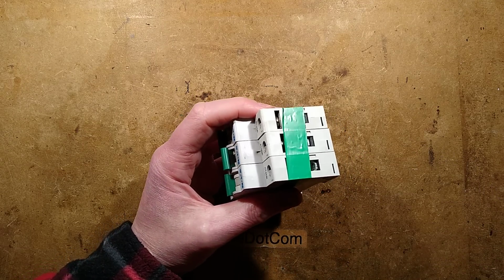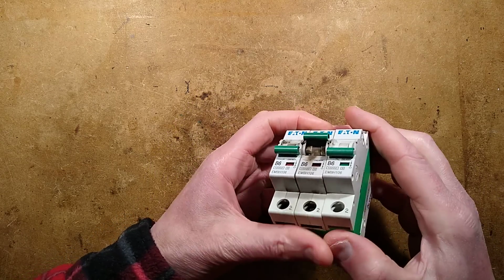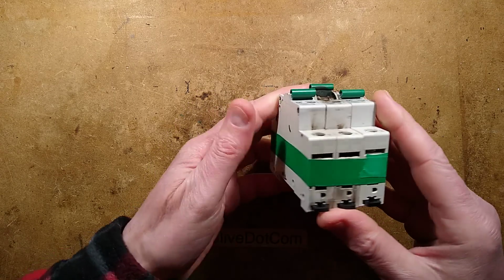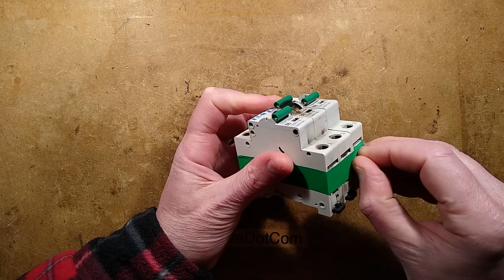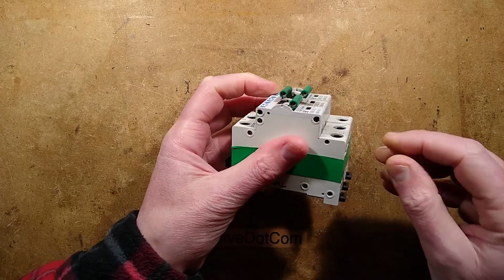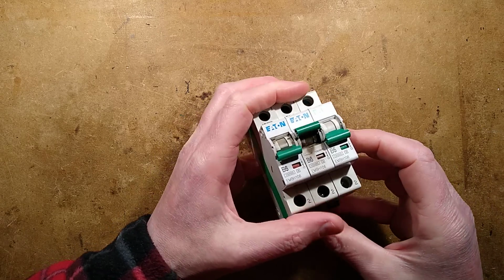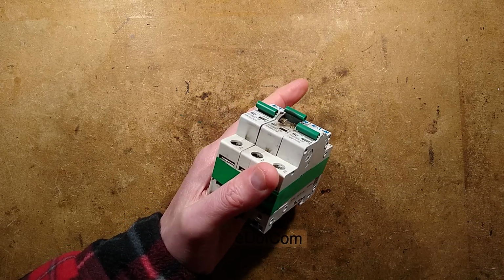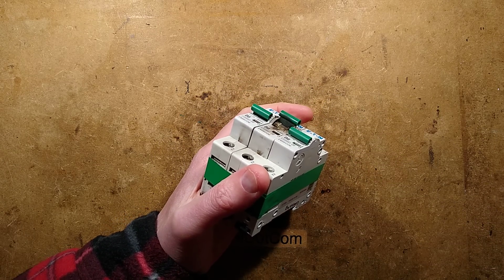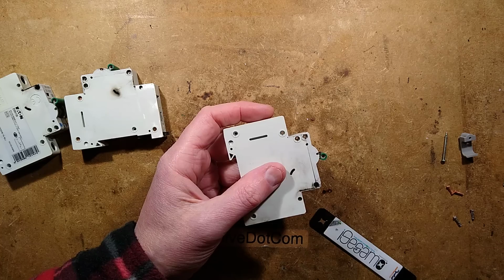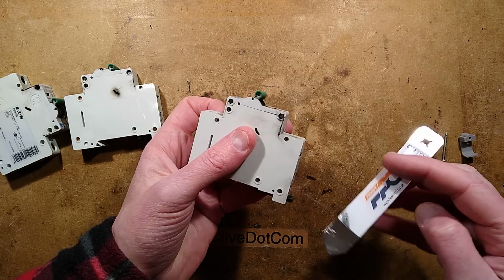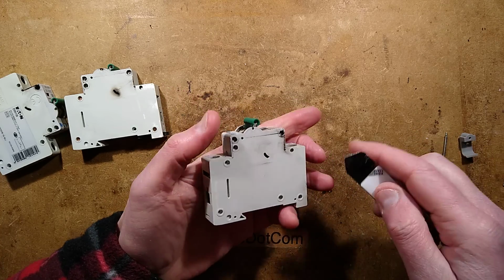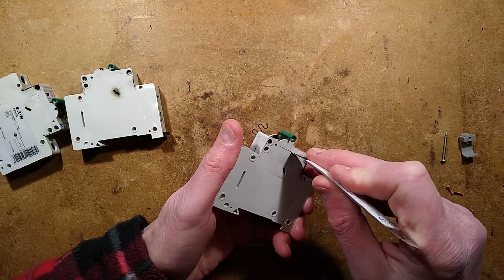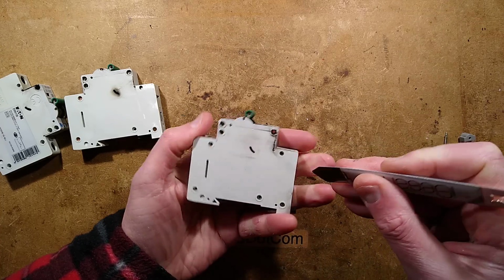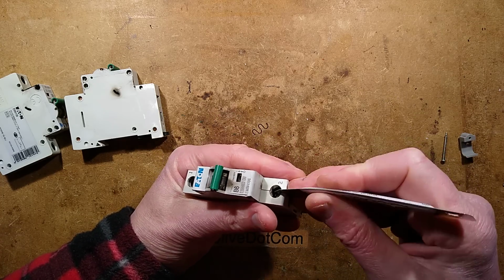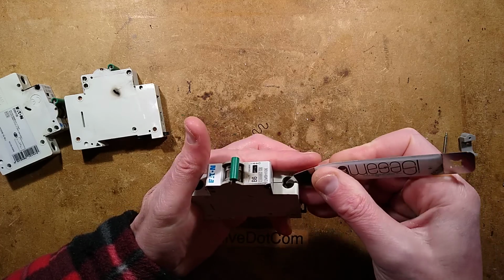So I shall take the tape off these and I'll drill the cases. And since it's going to take a moment to drill the rivets out of the middle breaker here, I shall pause while I do that. So one moment please. The rivets are out, let's explore. Now some of you may be wondering, why didn't they go and find the fault if it was a persistent fault like that? Well, the answer is because it was out of reach. It would have involved getting in some access equipment for that.